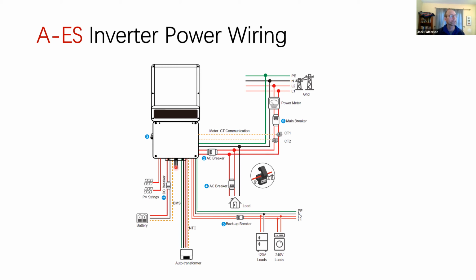And then in the middle, obviously, is that little Wi-Fi dongle, moving over to the auto transformer. Normally a PV inverter, and therefore also a hybrid inverter, wants to push out 240 volts. But if you've got a backup circuit that has 120 volt circuits on it, you need a neutral. Well, when we lose the grid, we lose the neutral. So we have to derive a new neutral. The battery and the inverter, this ESS, becomes the power supply, and a neutral has to be derived. And that's what the auto transformer does.